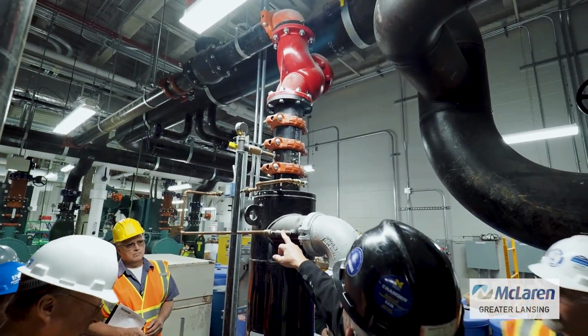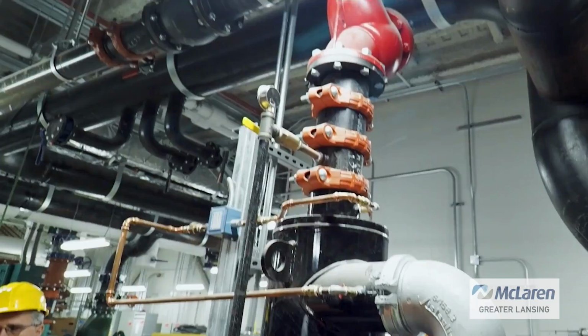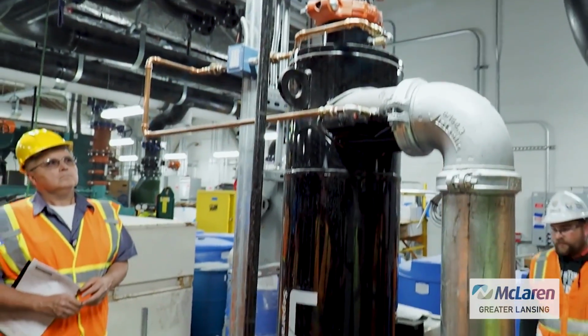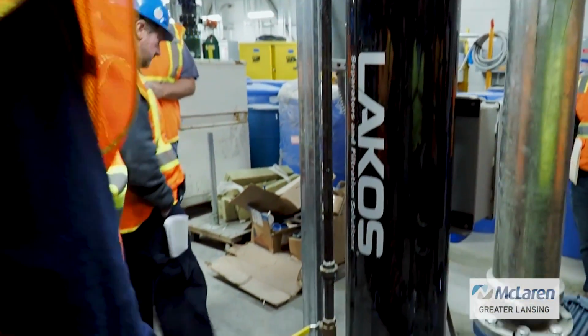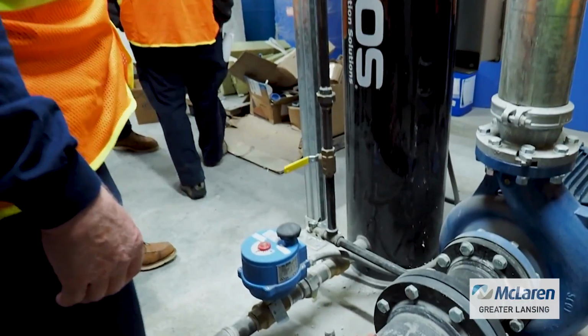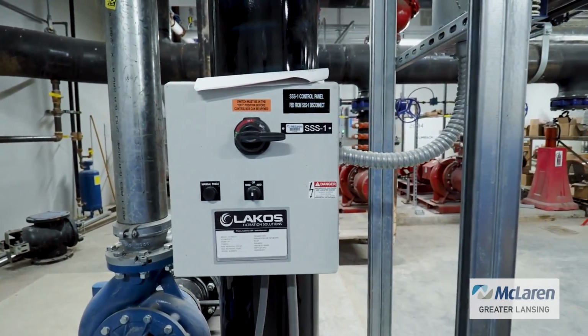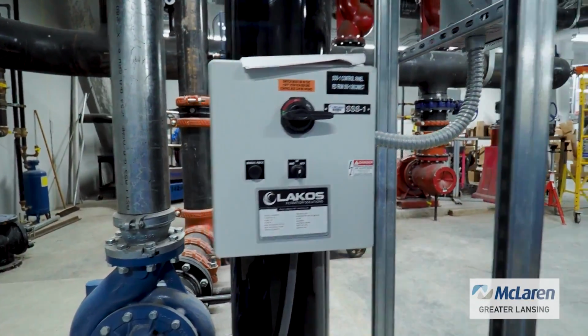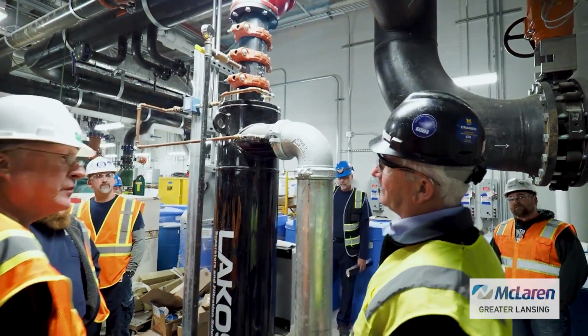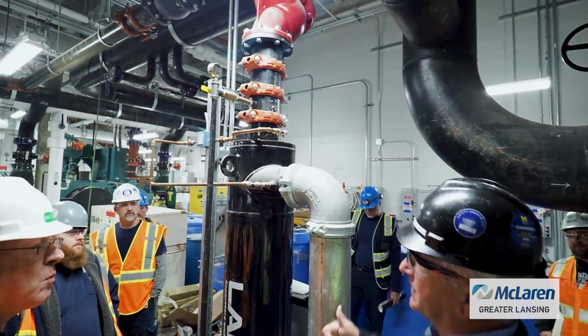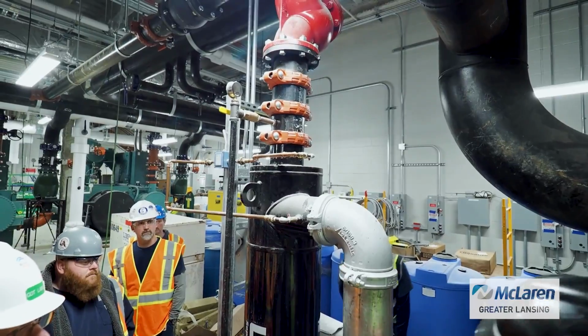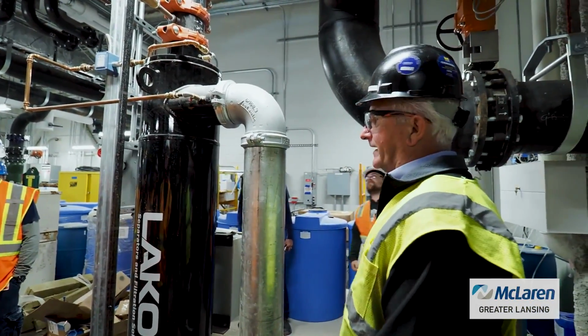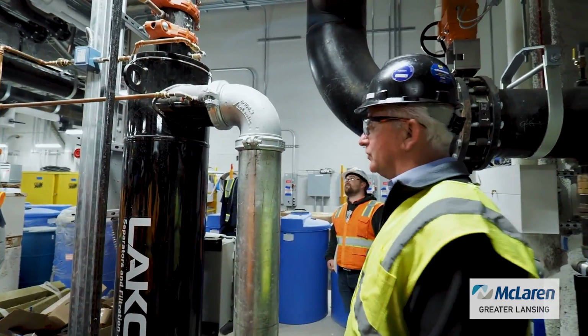There is a tap here, and obviously they're monitoring the pressure differential, although we're isolated here and here, but it looks like it's tied into the building management system. 12 would be the top end for the separator, where if you can get to 12, that'd be ideal. That's where you get the highest velocity. We're running it at design flow and getting the best performance out of the separator, getting those 45 micron particles removed.